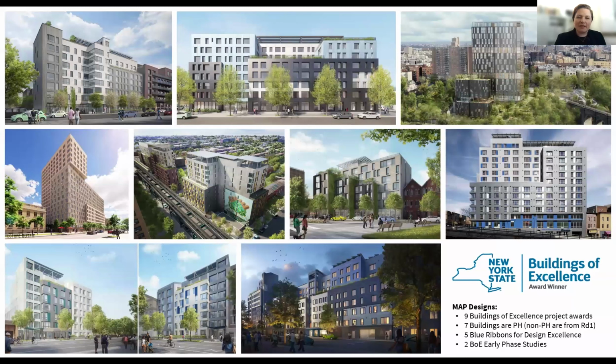Even though passive house multifamily is cooling load dominated, it still uses much less energy to cool than code minimum. And they often use split heat pumps, such as this building, which have an integrated energy efficiency ratio of 32, as opposed to window ACs that have an EER of 15. So they use about half the energy in the summer compared to window ACs based on the equipment alone, and then passive house reduces it even further from there.